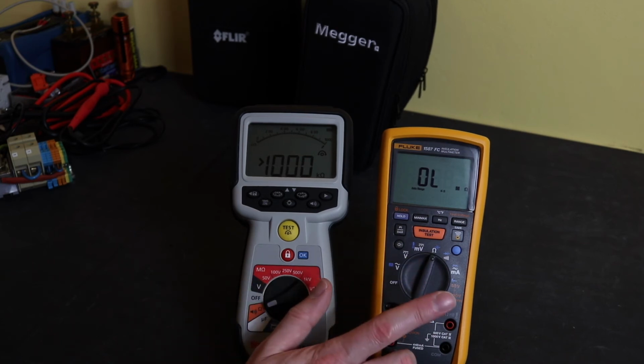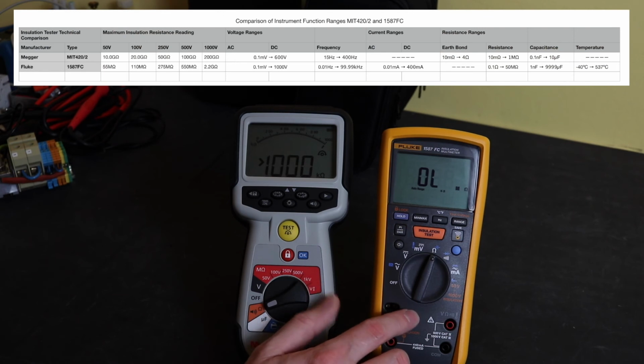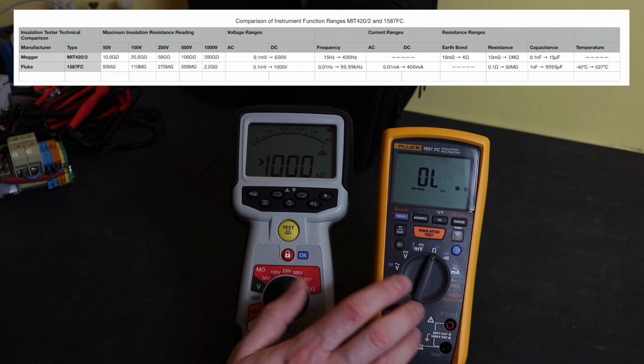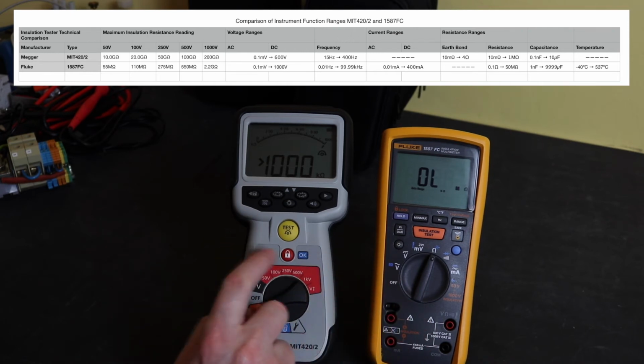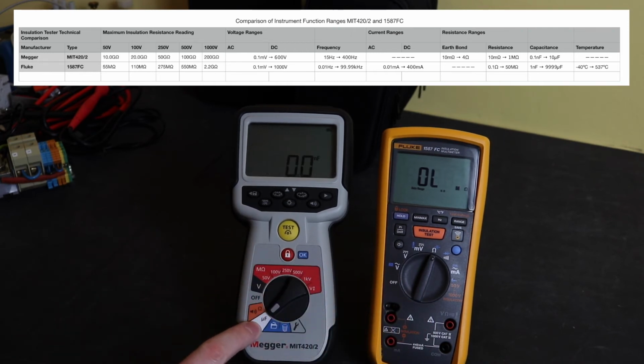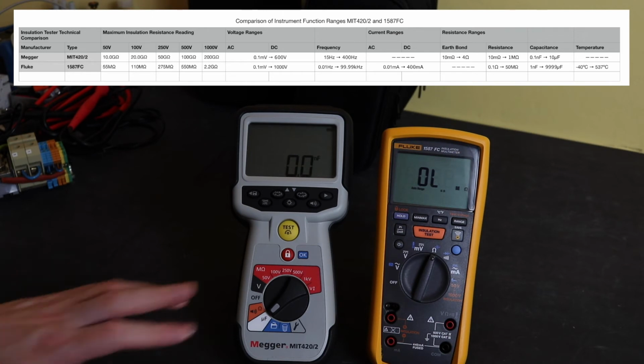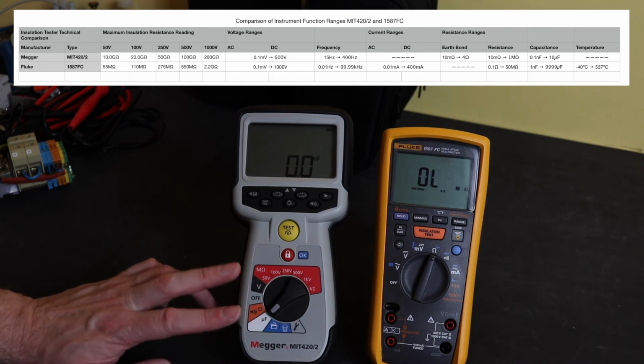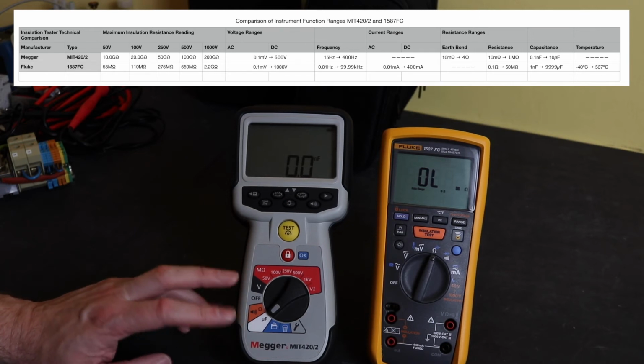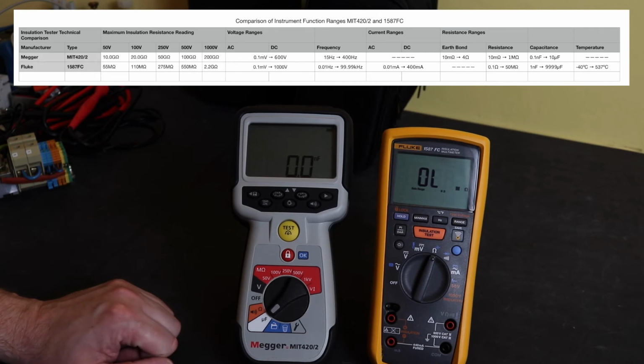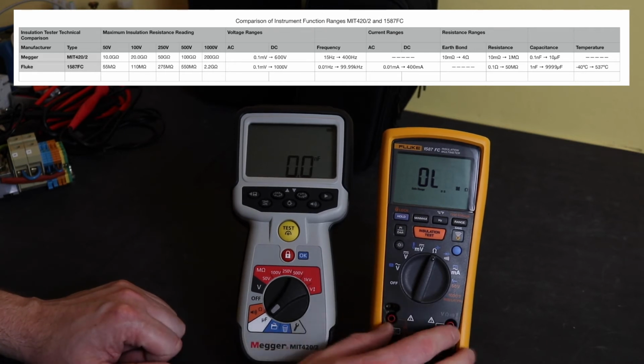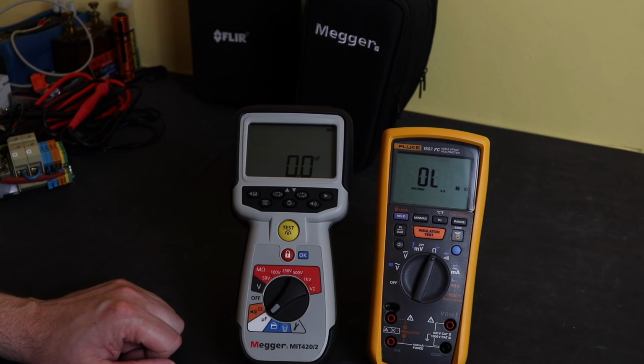Capacitance on this one, 1 nanofarad all the way up to 9.9 millifarads, so again another good range capability. In contrast, on the Megger, flick it round to microfarads, and you are actually 0.1 nanofarad up to 10 microfarad, and I do find that quite limiting for the electrical test aspects. Motor start capacitors quite frequently go above 10 microfarads, so it's a little bit limiting in that respect, whereas the Fluke can handle that higher capacitance level.